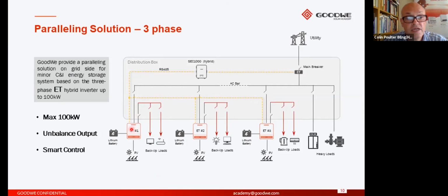Each ET will be connected to its own set of lithium batteries, and each one has its own individual backup circuit or essential circuit support. When there's charging and discharging capability, and the system is on grid, the SEC 1000 hybrid, connected by RS485 to each of these inverters, will intelligently control the charging and discharging of power across the whole combined effort of the batteries.